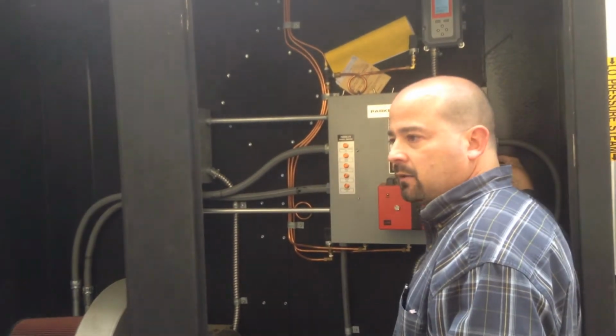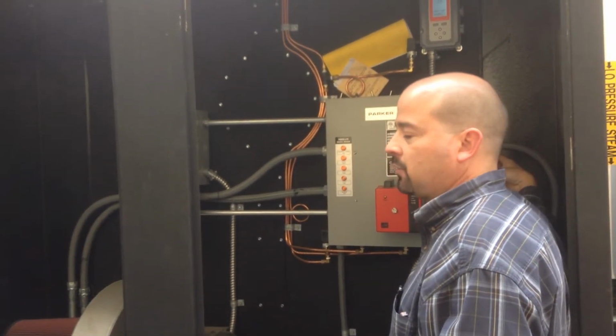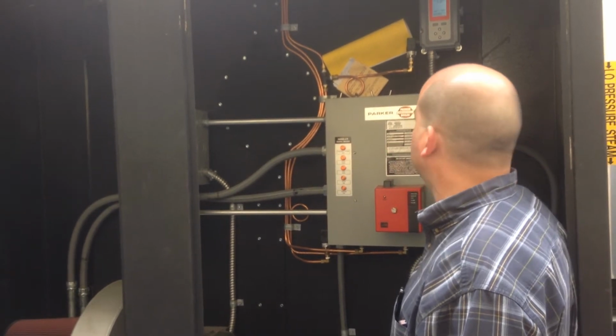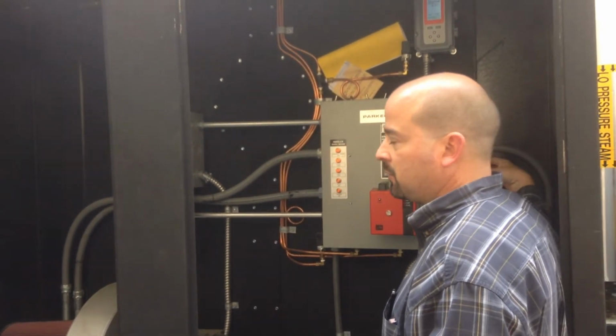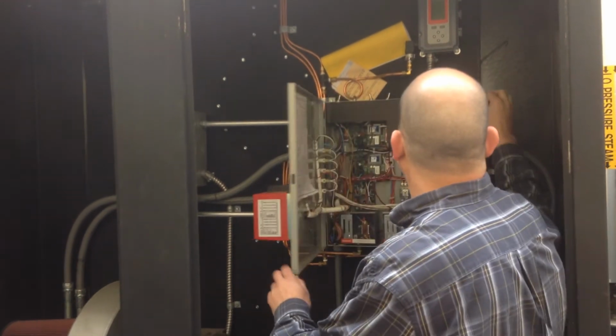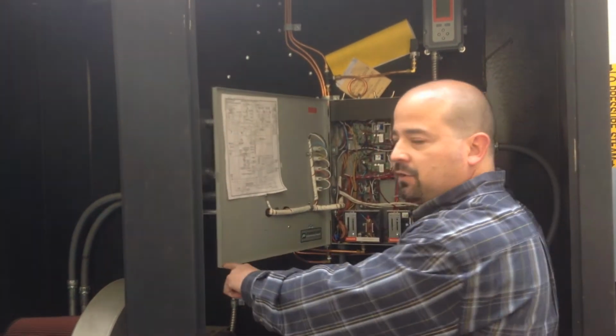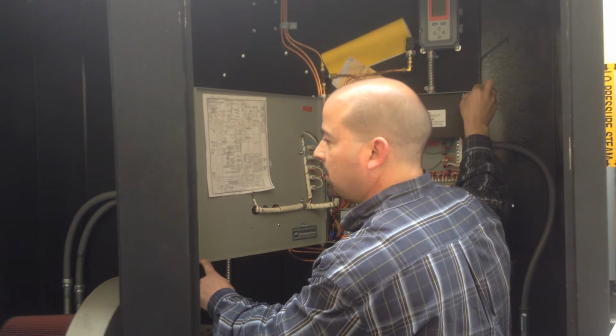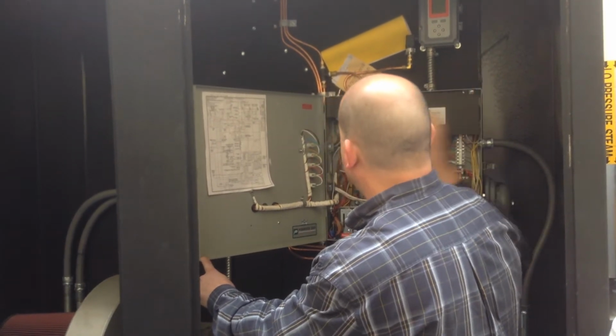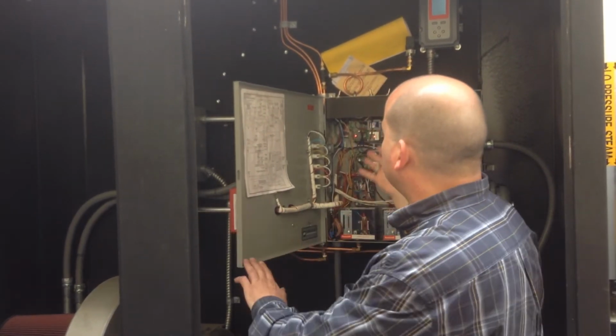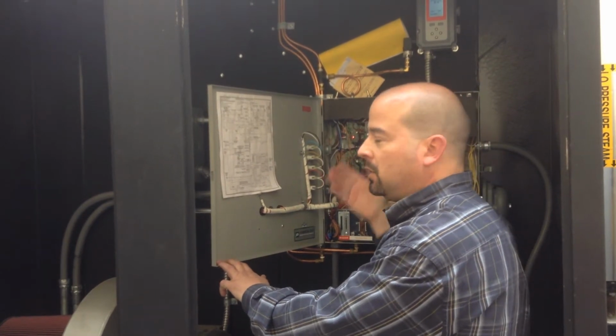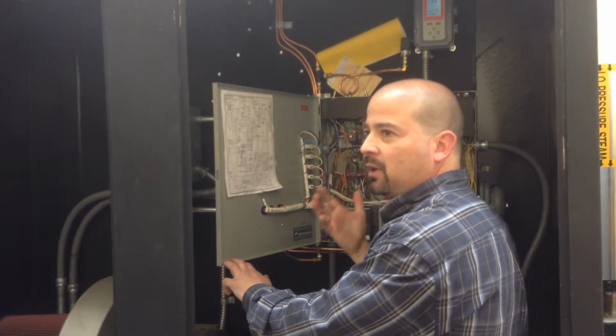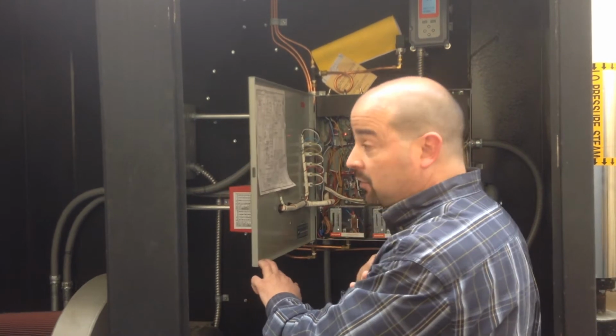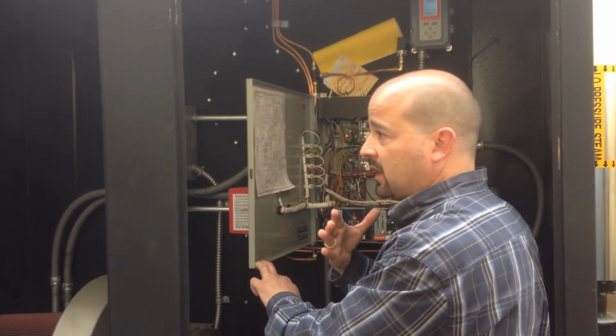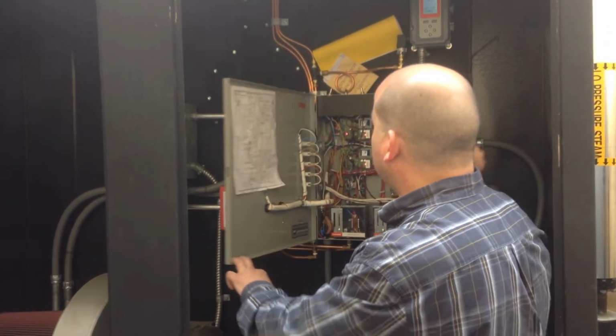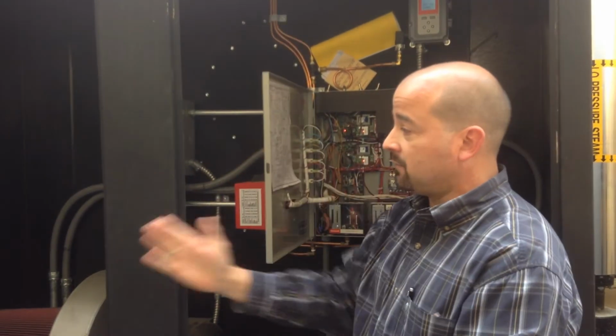If you open this panel, it will kill the power to the control circuit because there's a door safety switch up on the top right-hand corner, which I'm going to show you. It's right here. But you can bypass it if you need to do some troubleshooting by wiggling it and pulling it. A lot of times we might have a problem with, let's say, a water level control, but we can't see it in action and we want to see it happen. So a lot of times what I'll do as a service technician, my background is a service tech, I'll come out and pull it out and leave the panel open, put these covers on.